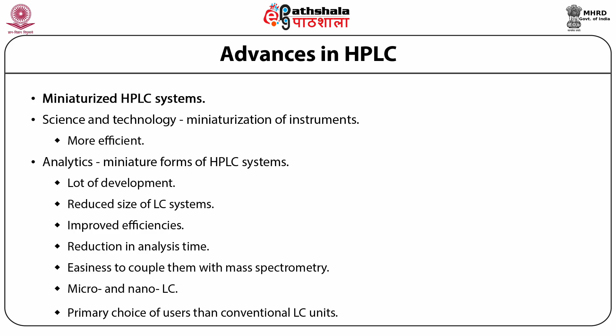Ultra performance liquid chromatography, which is also known as UPLC, is an advanced and recent version of liquid chromatography that utilizes the principle of HPLC. Use of smaller particles as column packing material is the key of any HPLC system, which is essential for increasing efficiency and resolution. Now it is well known that particle size less than 2.5 micron offers significantly increased efficiency and resolution. Thus, it is believed that efficiency and resolution of LC systems can reach new limits by using further smaller particles, and the same idea has given rise to UPLC.